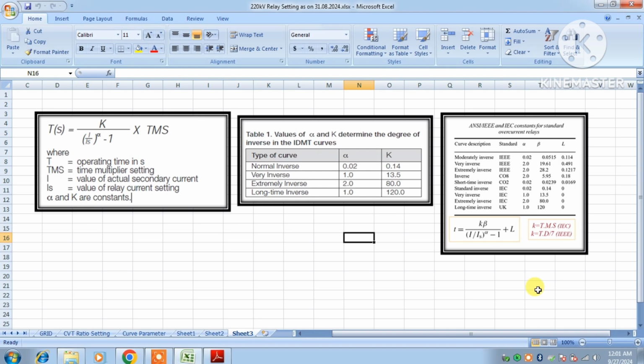Utilizing this application, we can easily find out how much time the relay will take if a particular curve is selected. Second, it is helpful for relay coordination. So upstream and downstream breaker coordination, or fault clearing coordination, we can also do easily. Third, if there is a fault analysis system, suppose we have disturbance recorders, then as per the relay settings we can find out at which time the relay operated.